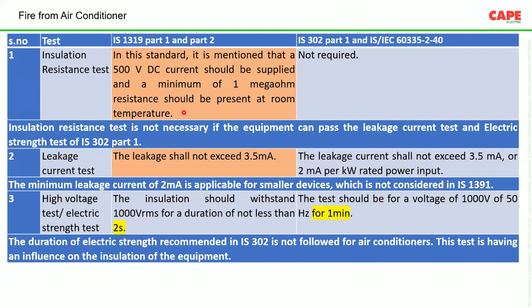We made a detailed study and we are trying to publish a report. For example, point number 3, the high voltage test, the electric strength test, which is very, very important for an electrical appliance because most often failures are due to insulation failure. IS 1319 asks for a 1,000-volt test for 2 seconds. That means between the phase or neutral conductor and the body, 1,000 volts is applied for 2 seconds and the equipment shall not fail.